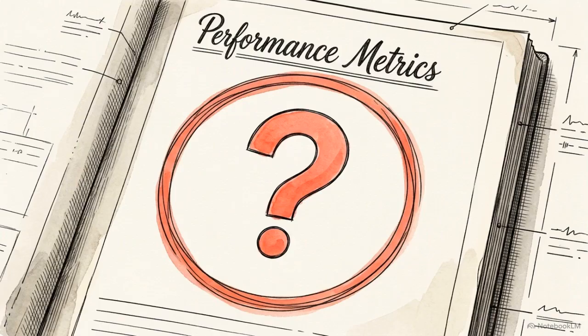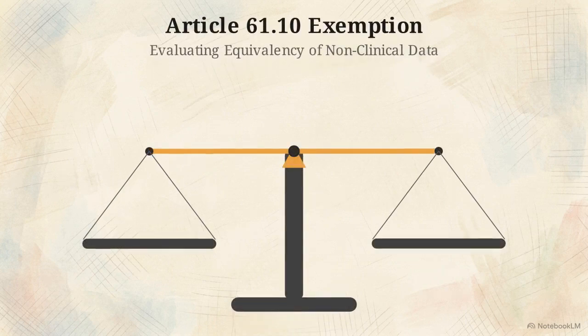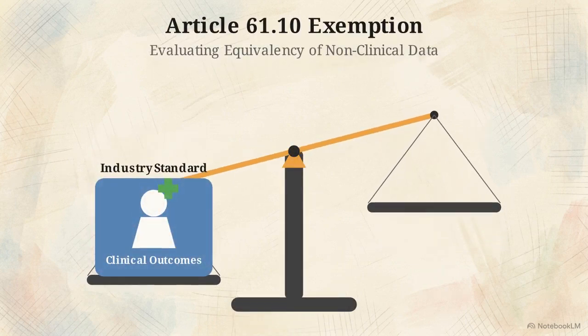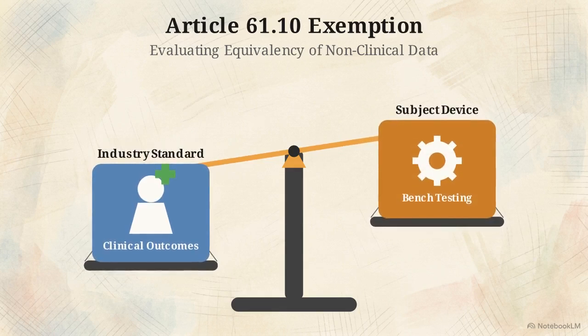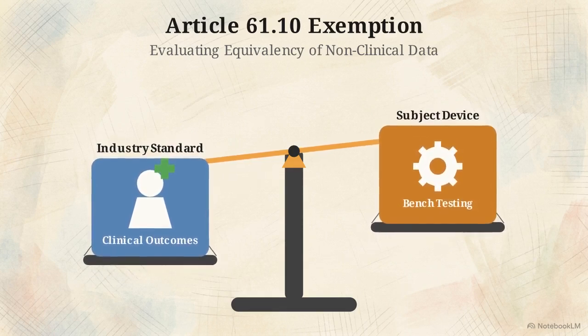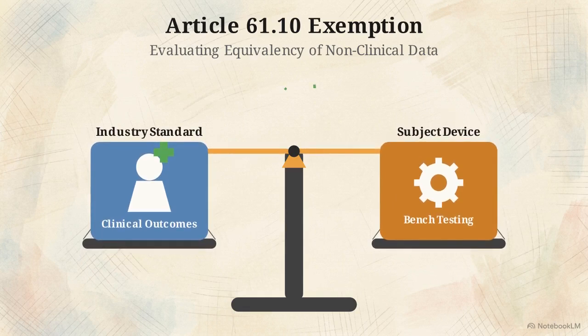Notified bodies consistently identify the same deficiency. Manufacturers often fail to define measurable, device-specific parameters within this analysis, preventing a valid comparison between their bench tests and the industry standard. This scale shows how reviewers evaluate your data. They weigh your non-clinical evidence directly against the established clinical outcomes of the industry standard to determine if bench testing can adequately replace human data. A poorly constructed state-of-the-art analysis guarantees failure before the reviewer even opens the rest of the technical file.